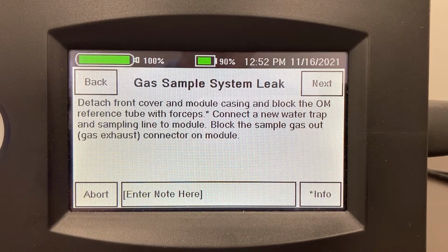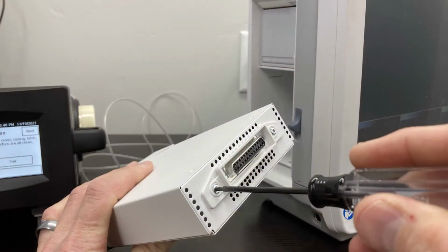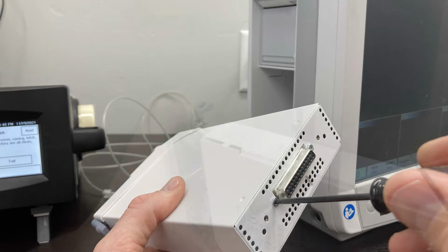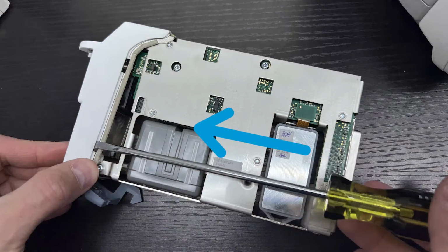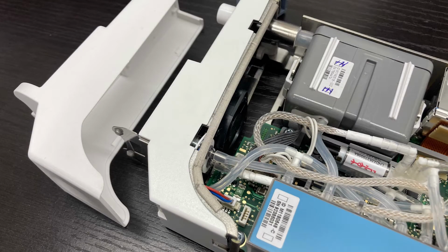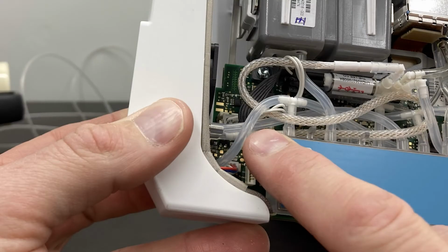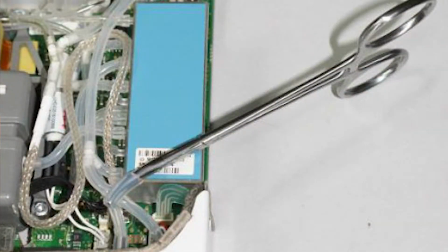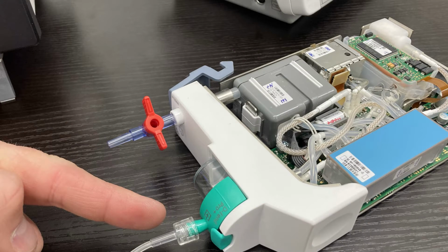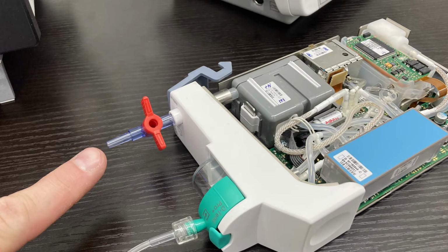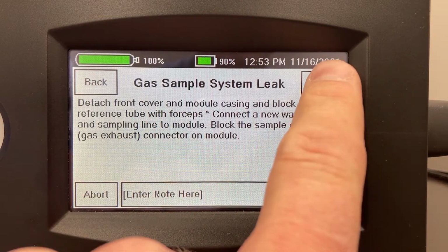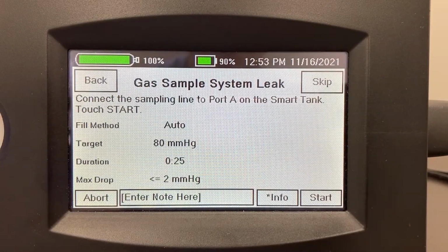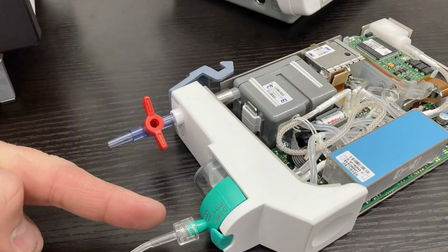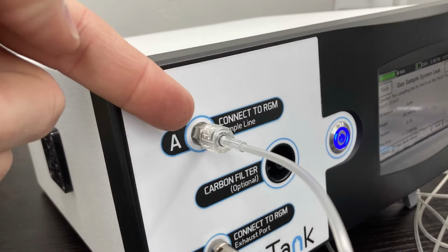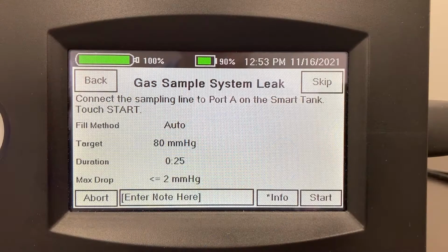Now we're going to prepare the unit to do the gas sample system leak test. We've got to detach the front cover of the module as well as the casing, and then we'll block the OM reference tube with forceps and connect a new water trap, and we've got to block the sample gas outlet connector. We then connect the sample line to port A on the SmartTank and hit start.